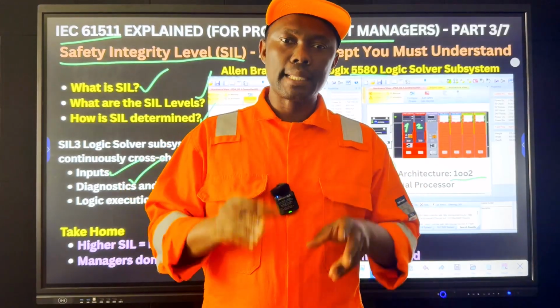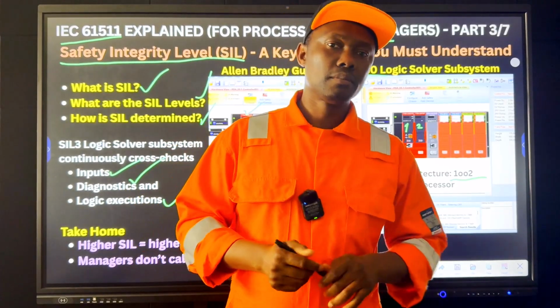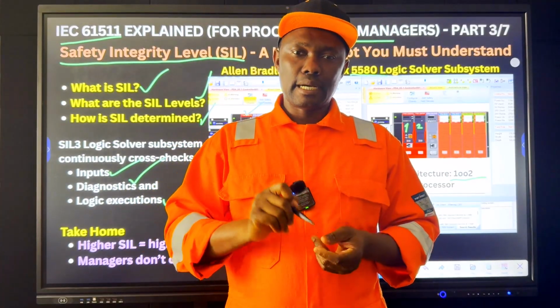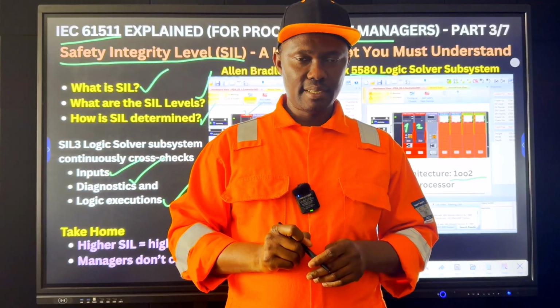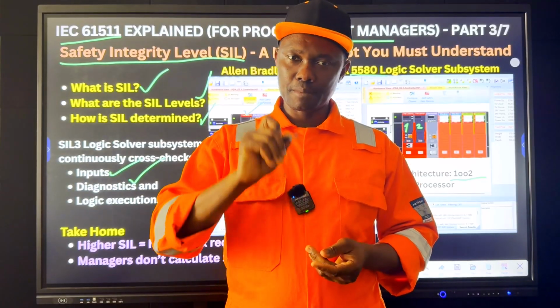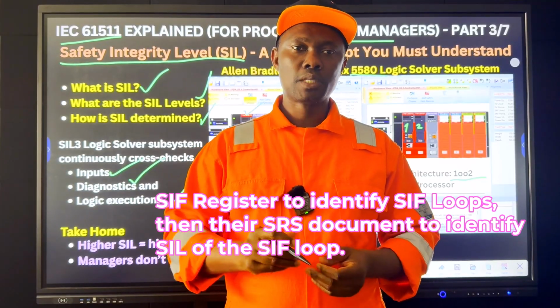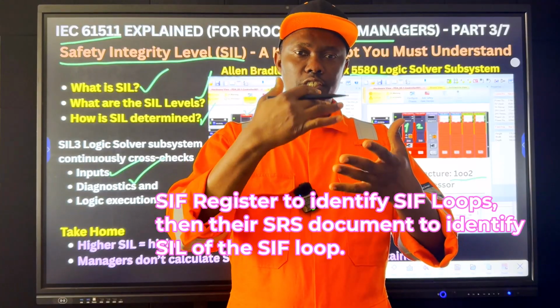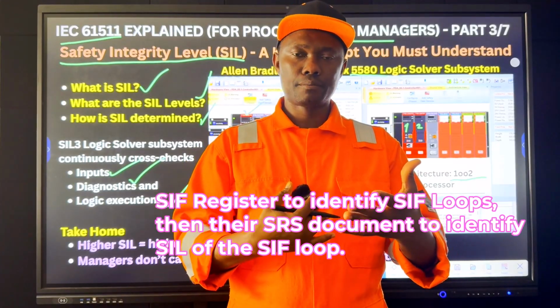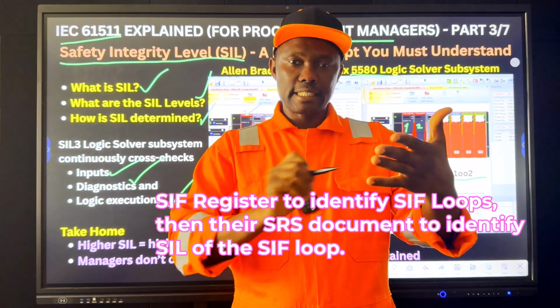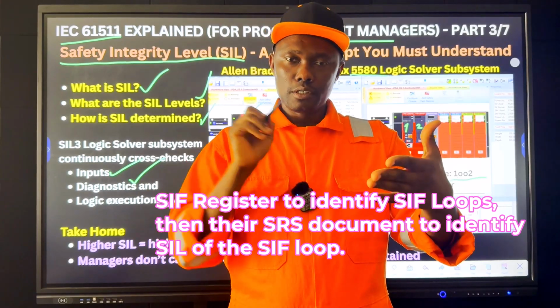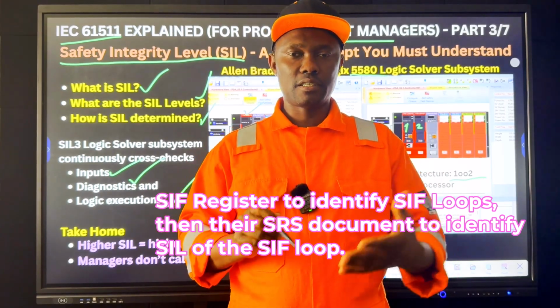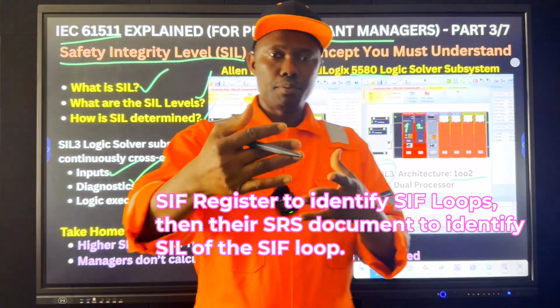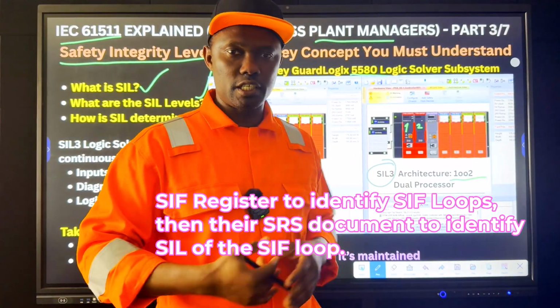So the point to note is that managers do not calculate SIL, but it's your responsibility to ensure that SIL is maintained in your plant at all times. And one thing I would want you to do for me after watching this video, as a plant manager, is to go through the SIF register of your plant and try to identify each of the SIF loops and the safety integrity level of it. At least that will help you to relate to what we've discussed in this section.